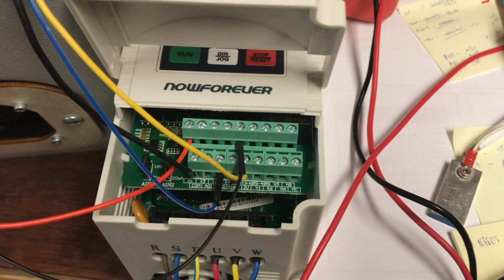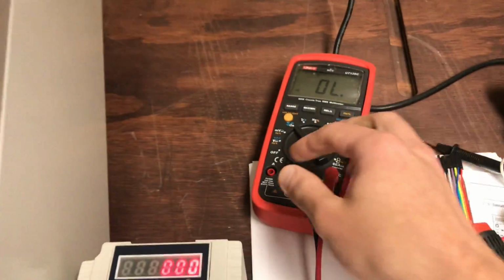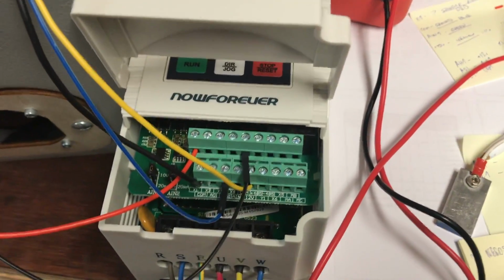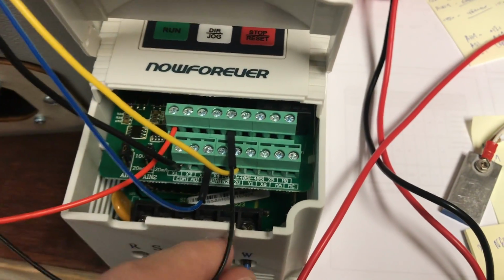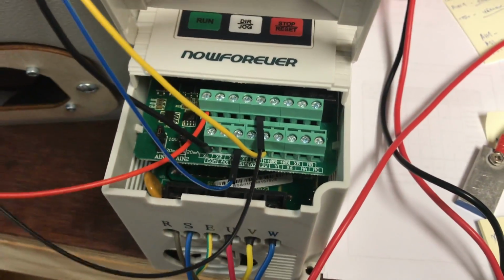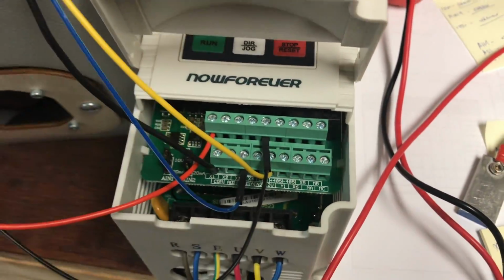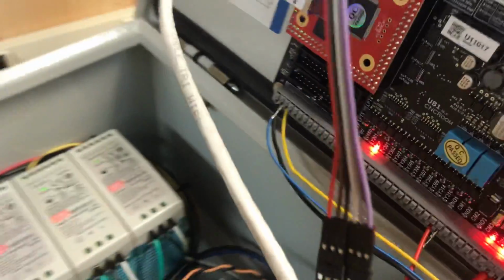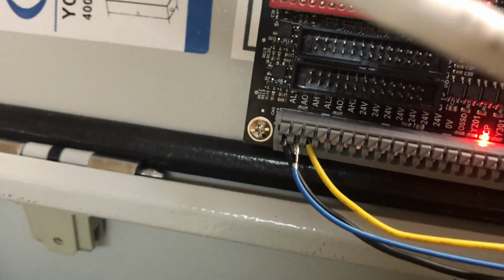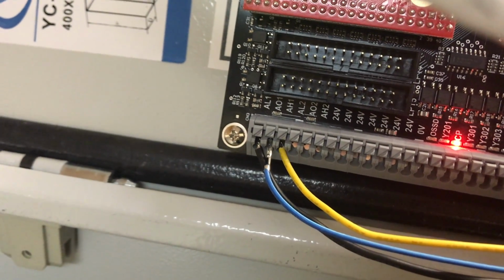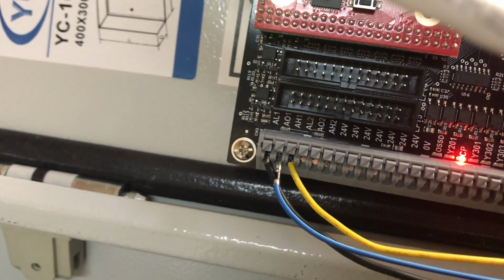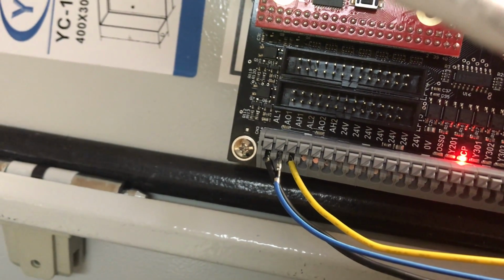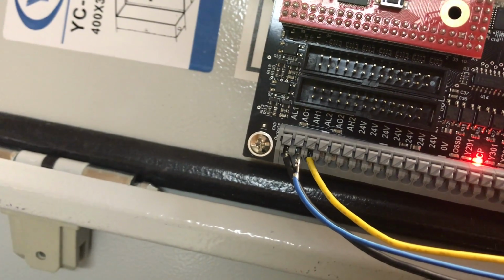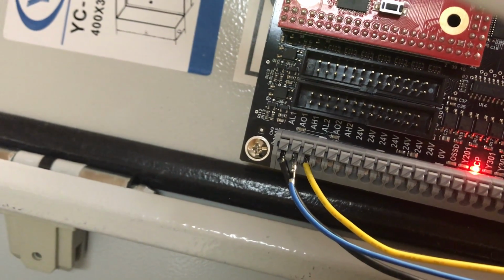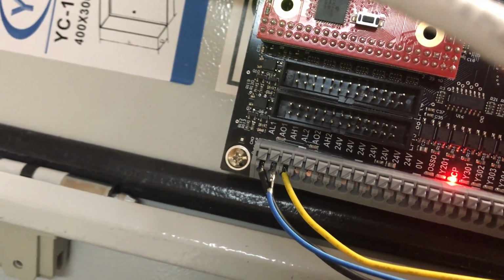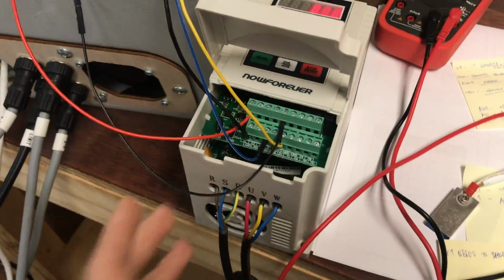Of course, for the speed control, we have the common wire, we have the analog in one, and we have the yellow wire for plus 12 volt. And these go to the analog speed circuit right there. So we have common going to AL1, we have the 12 volt going to AH1, and we have the blue wire going to AO1. Oh, did I mess that up? Okay, so black common goes to AL1, and the blue analog input goes to AO1, the analog input on the VFD.